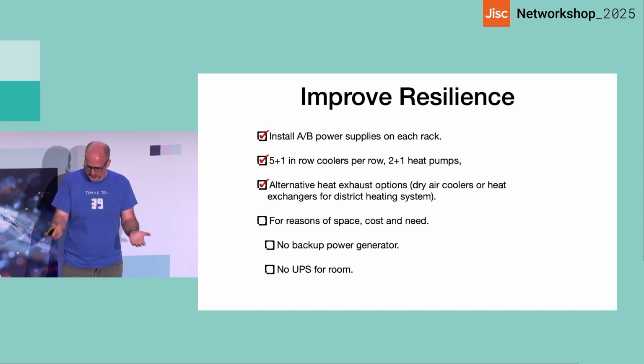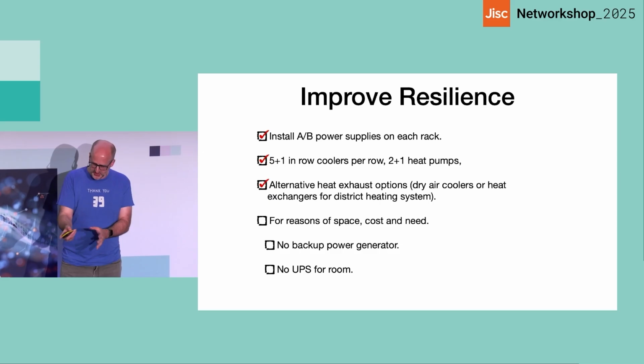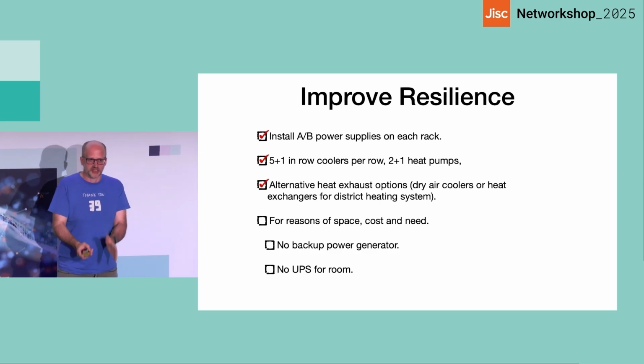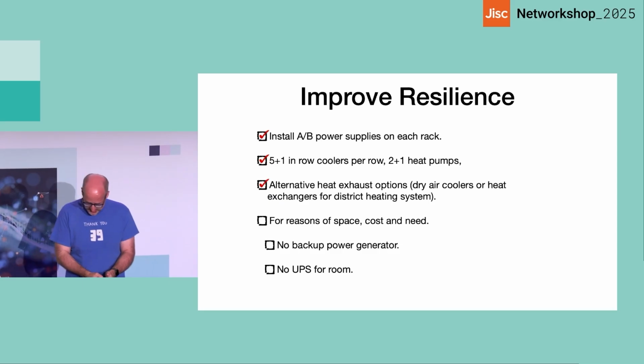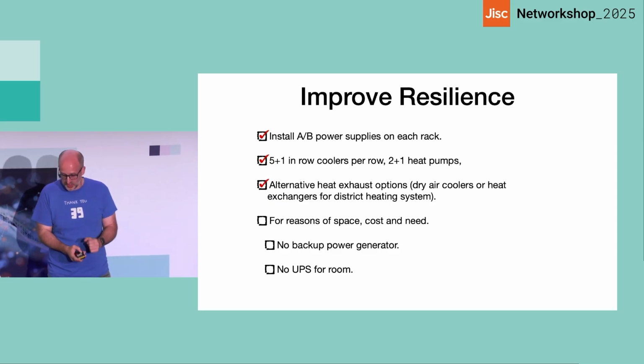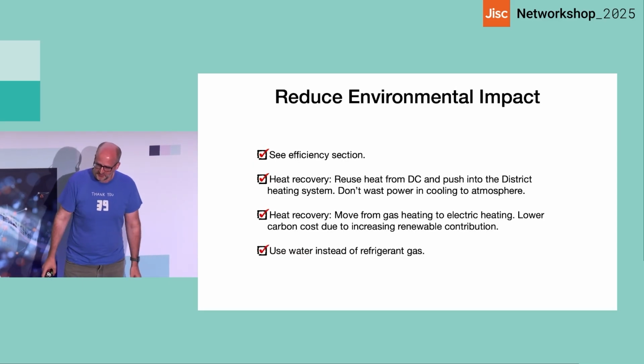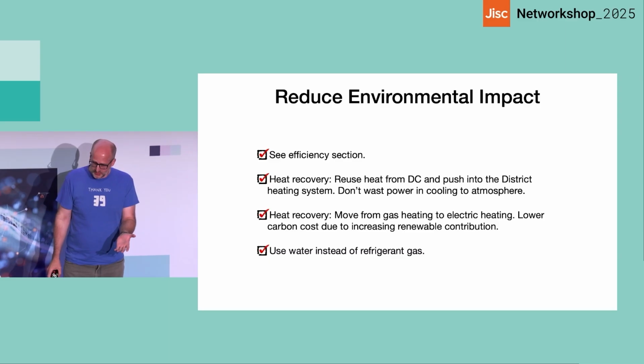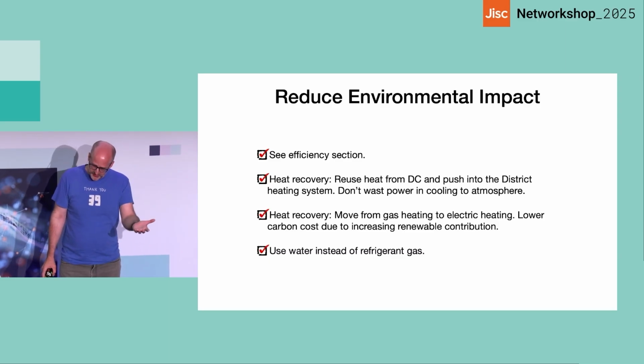If that happens, we've got 2+1 heat pumps. We've got alternative options for the heat exhaust, the dry coolers, or the district heating system. As I mentioned, we have no backup power generator or UPS for this room, but the equipment in this room doesn't need that level of resilience. It would have cost a lot more as well. Reduced environmental impact. So we've got the improved efficiency.